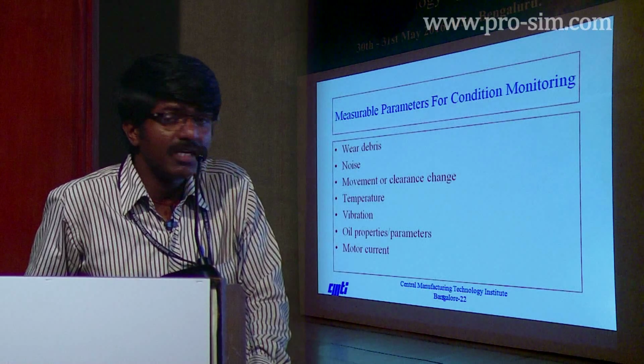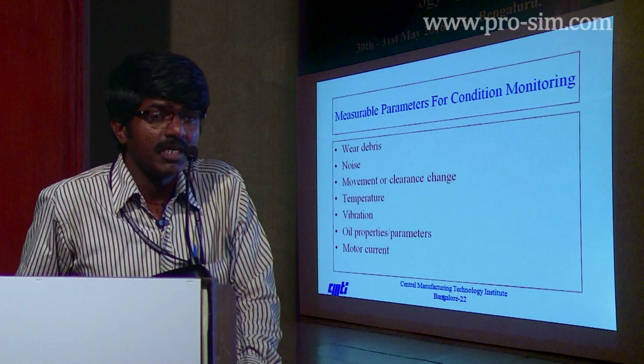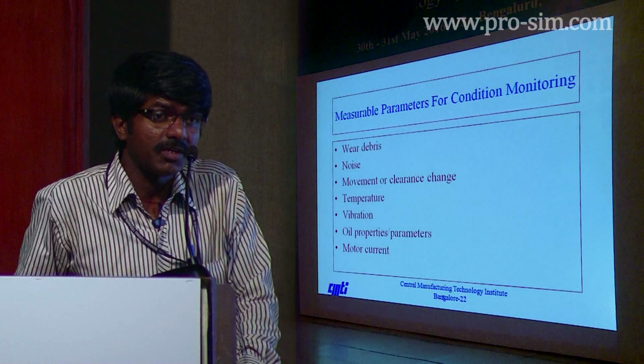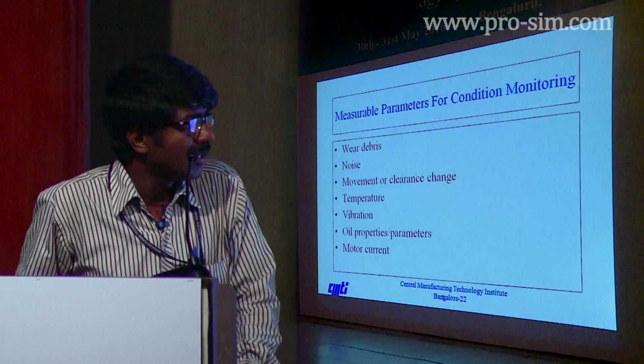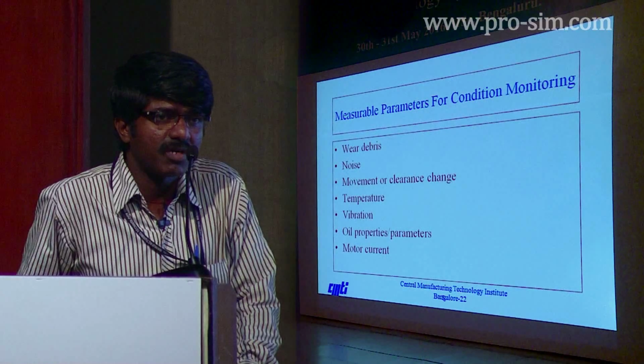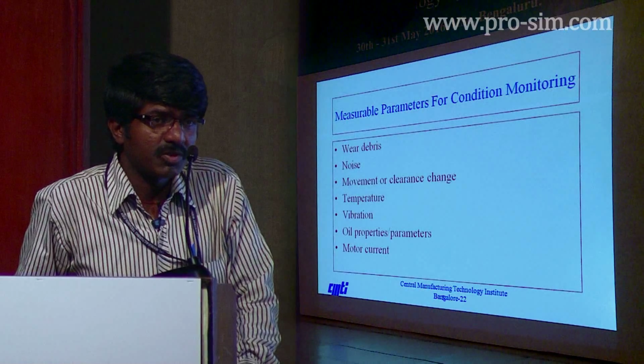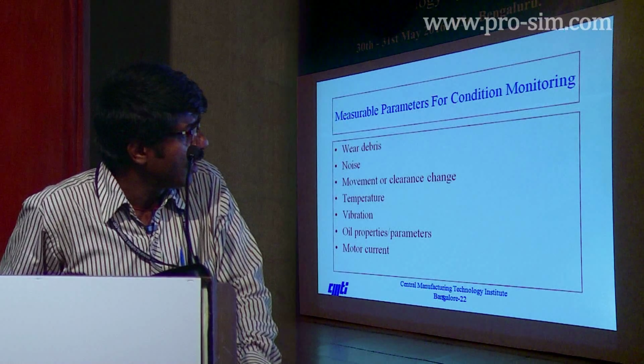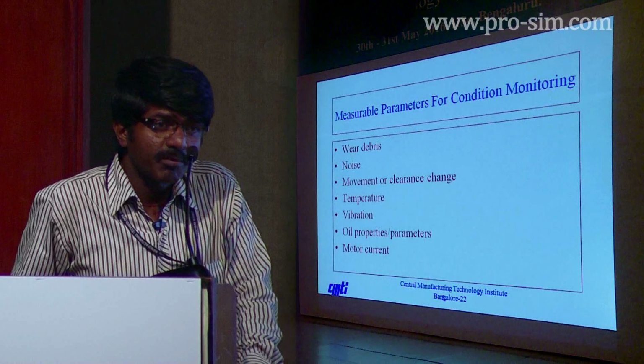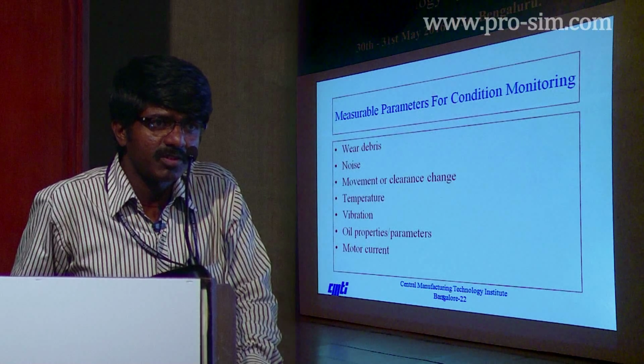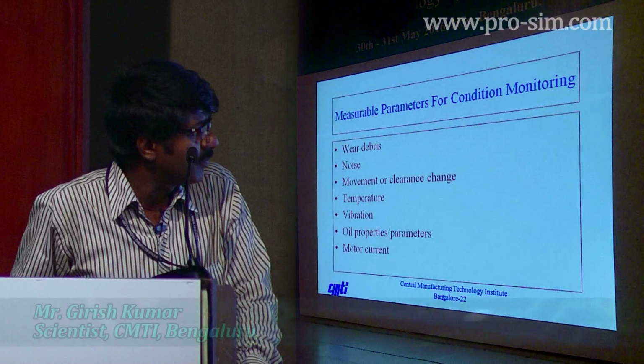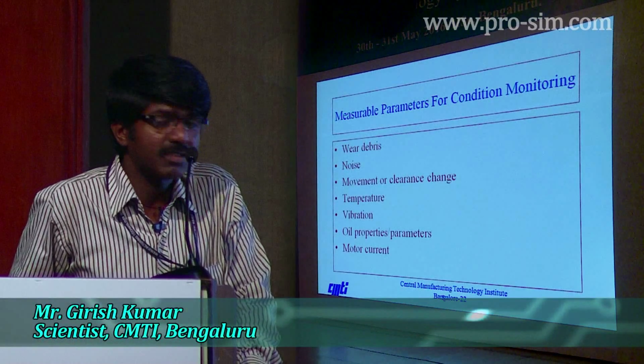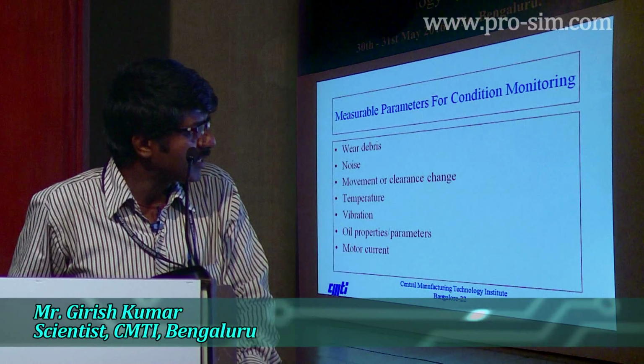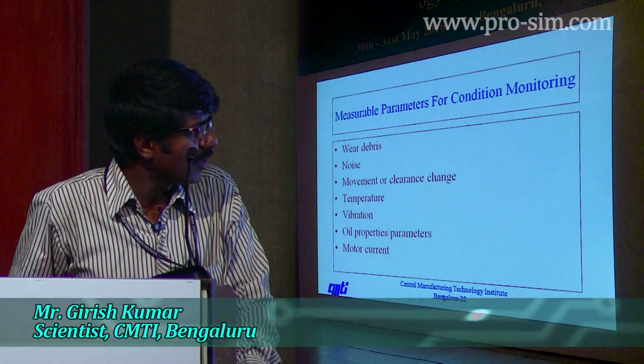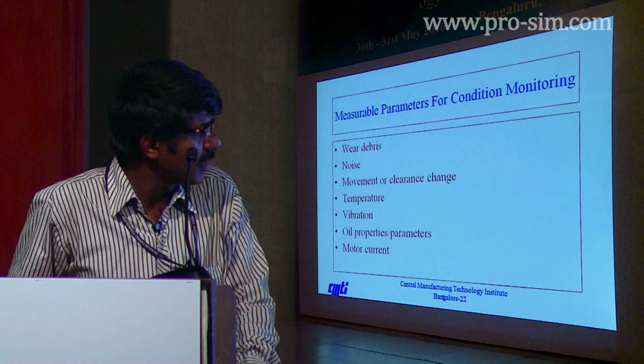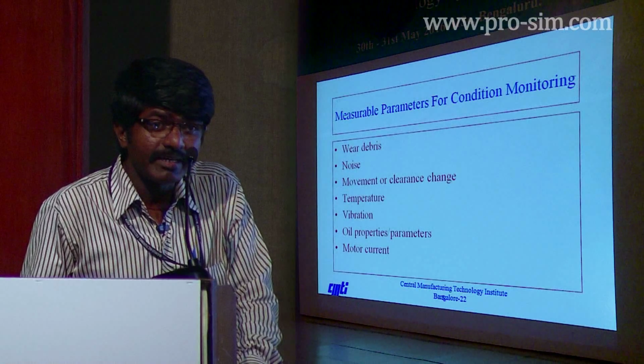This technique is very widely used in large machines like turbines, hydrostatic machines, hydrodynamic bearings, wherever it is there, they will use it to monitor the gap between the stationary part and the moving part. Whenever it becomes very close to the stationary parts, automatically the machine will trip off. Okay, temperature. So we can use temperature also for monitoring the health condition of the machine. Nowadays thermography is quite popular, and vibration, it is scientifically proven. We will discuss why we are going to use vibration in the coming slides. Oil properties and the parameters. Okay, for proactive maintenance this is a must, and motor current if you are using electrical machines.